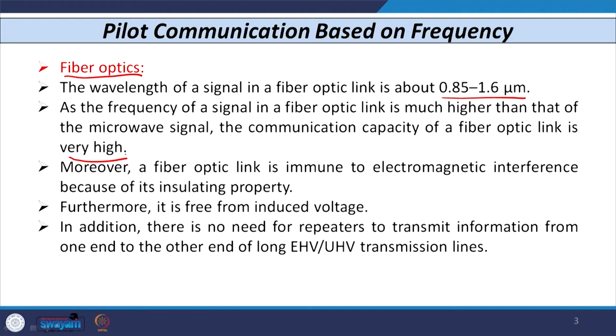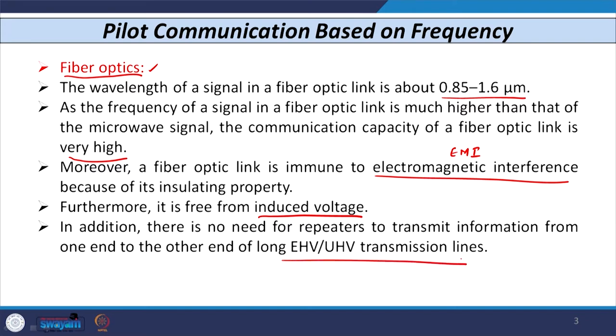Moreover, the fiber optic link is immune to any electromagnetic interference, so there is no EMI interference. Furthermore, it is free from induced voltage — the problem of induced voltage on parallel conductors is also rectified with fiber optic. In addition, there is no need for repeaters to transmit information over long EHV transmission lines. Because of all these advantages, fiber optic communication is widely used nowadays.